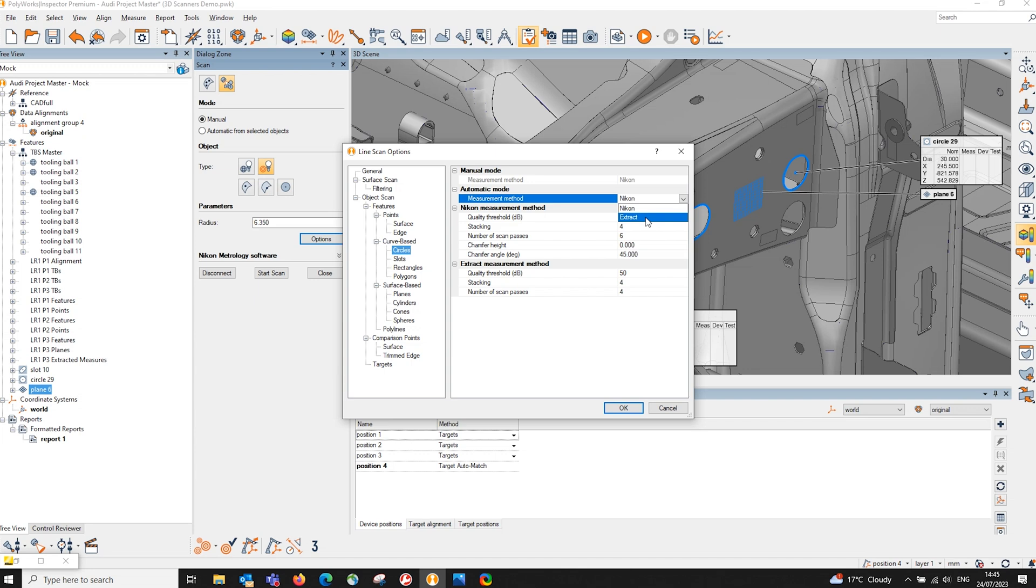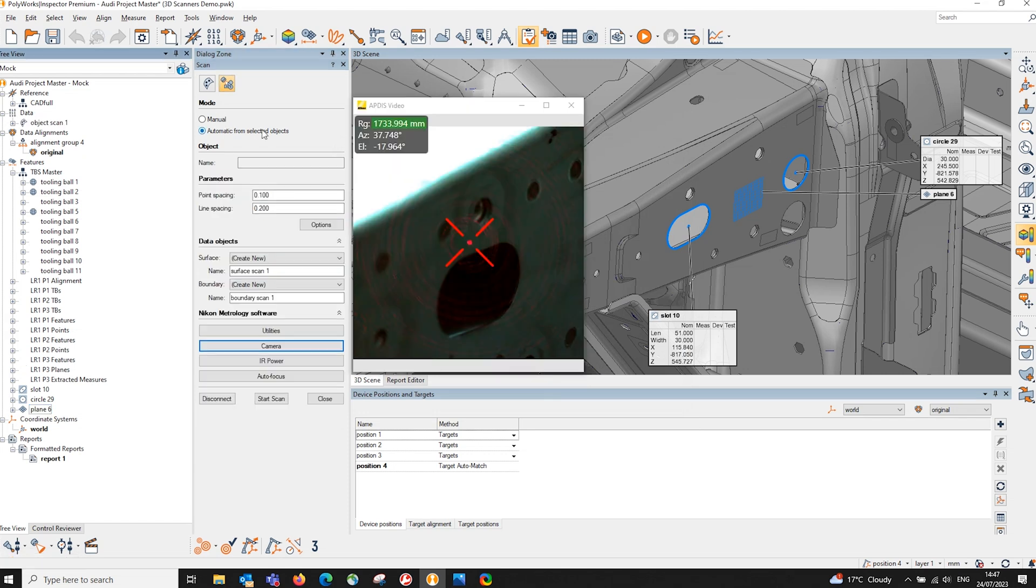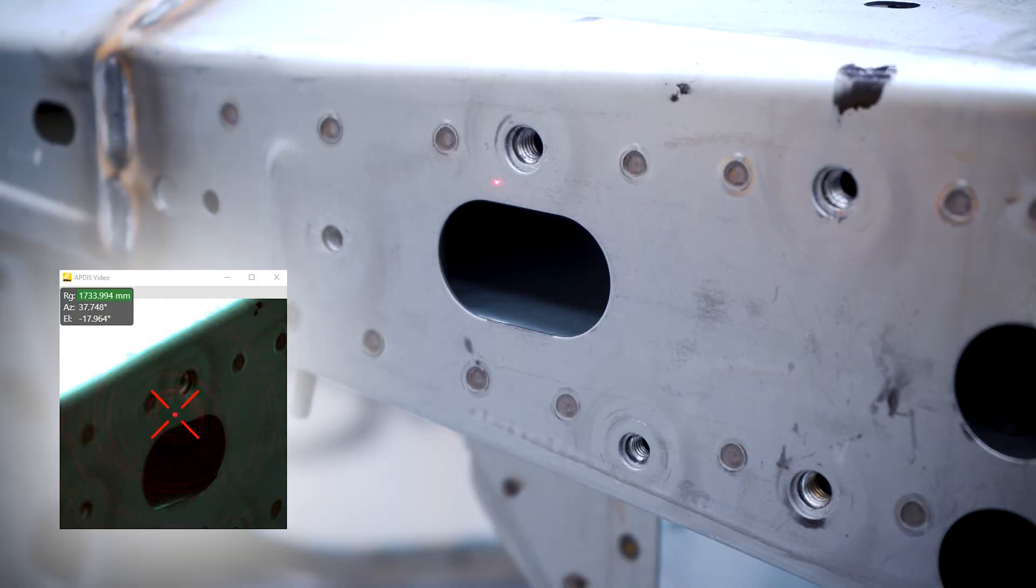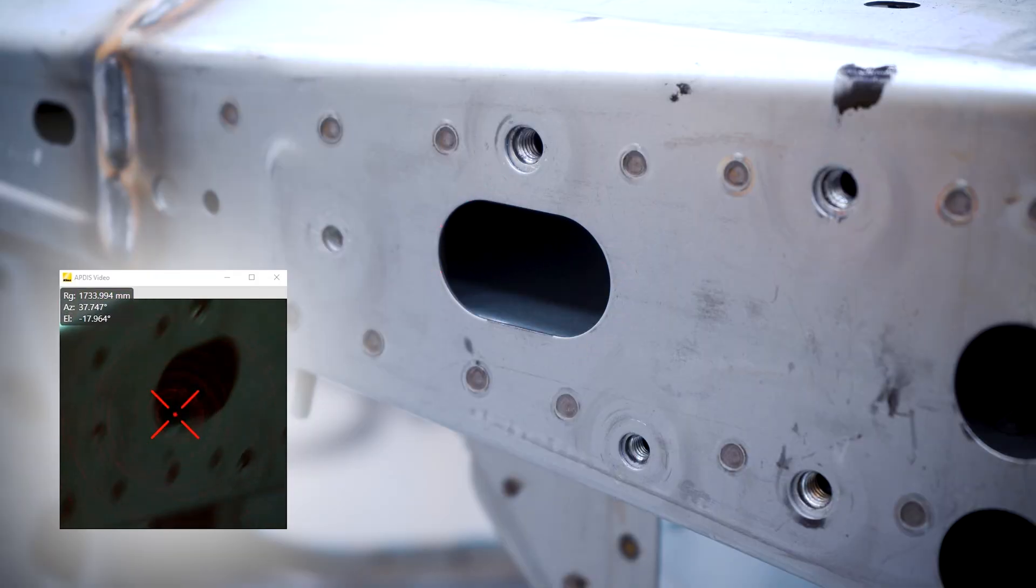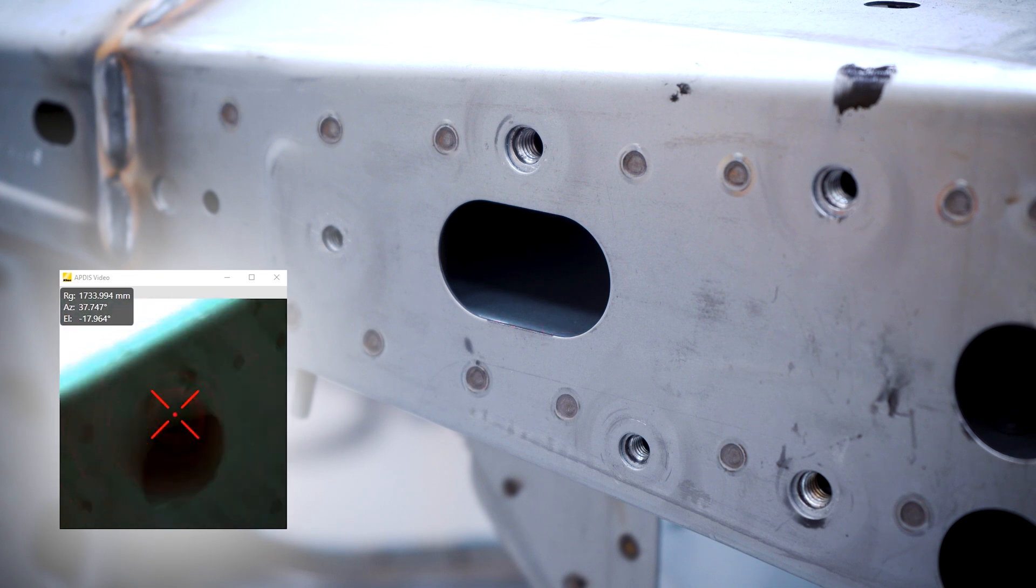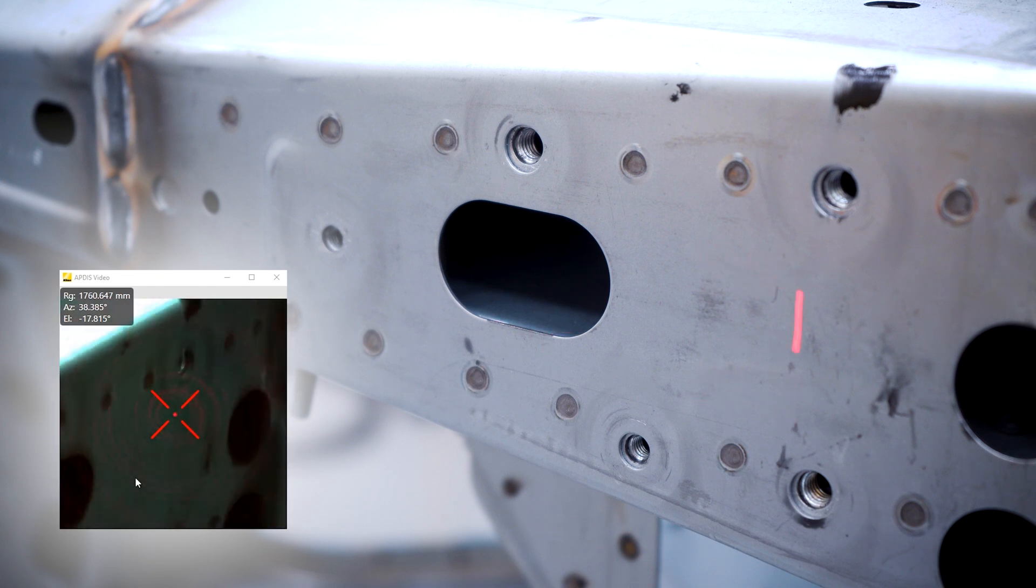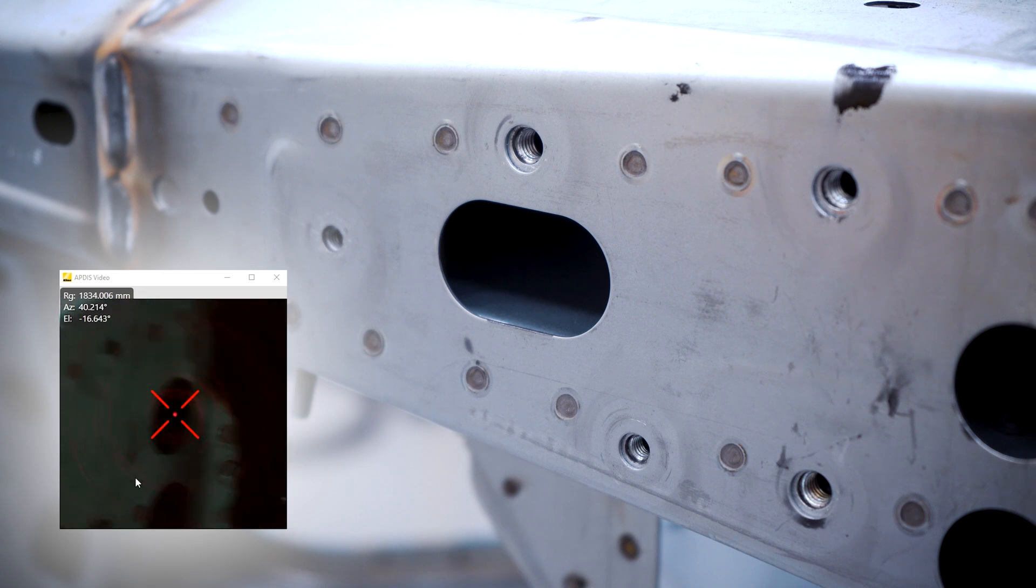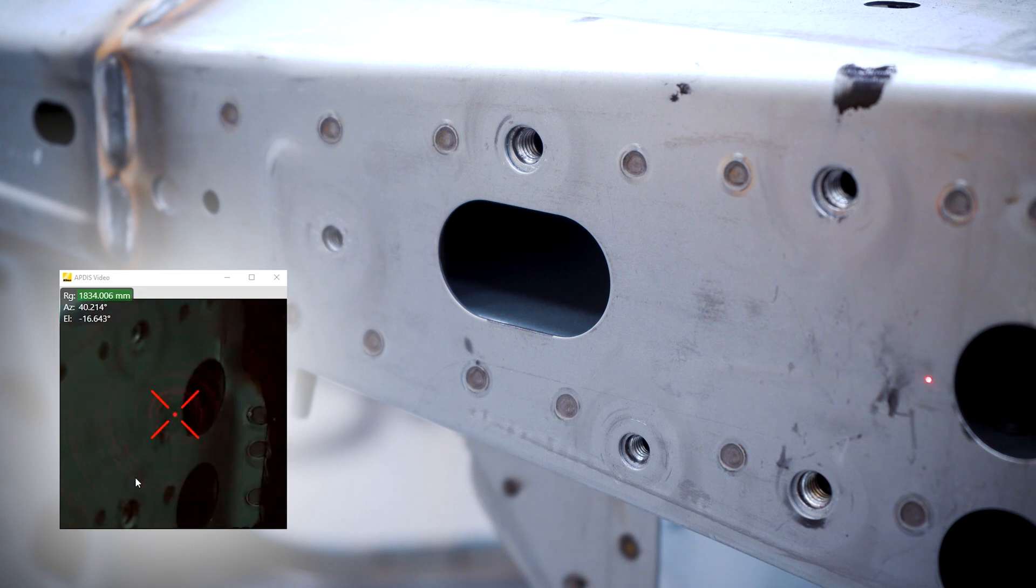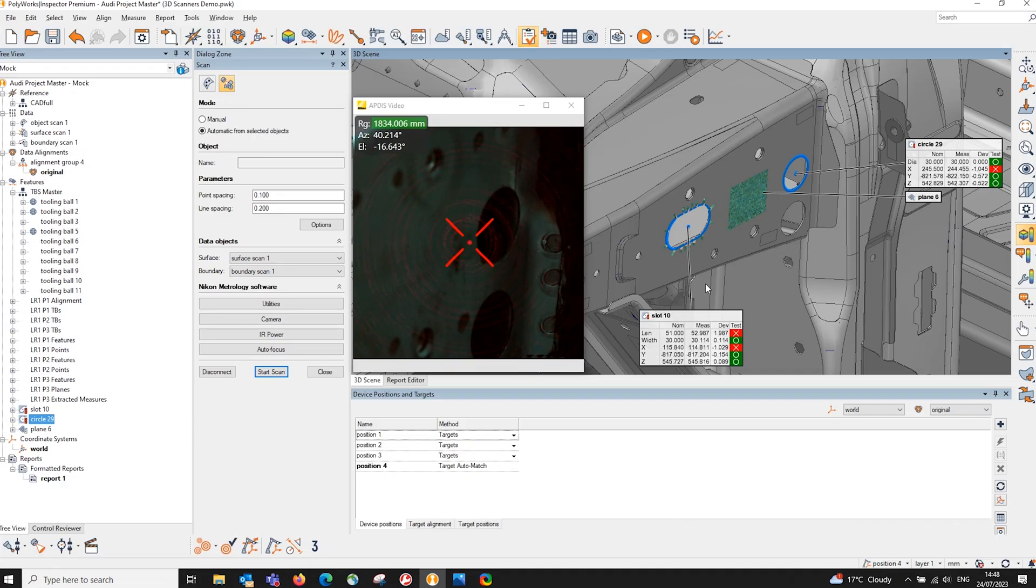Extract keeps the raw data and lets Polyworks do all the work - the calculations - and gives you the points to see so you can further analyze the information if need be. With that I can use my automatic option. We have our point spacing, line spacing and we can specify what data or boundary data we're generating. I'll highlight my features that I wish to measure, hit start scan and the system will automatically know where to go because we're aligned to it. You can see it does its own little pattern to measure the points on a surface or around the edge of a hole and then Polyworks is able to extract the information to give us our results.